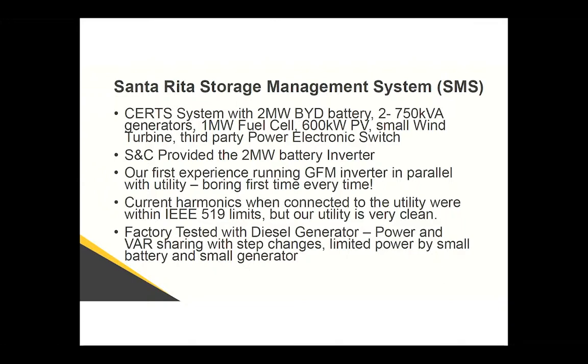One of the concerns we had was, okay, if we're a voltage source and we're running in parallel with the utility, what do the current harmonics do? So at our shop, we measured what the current harmonics were. They were actually within limits, but the sort of unfair thing is our utility voltage harmonics are on the order of 1%. So it was a pretty clean utility, clean inverter, so we didn't really have any current harmonics.